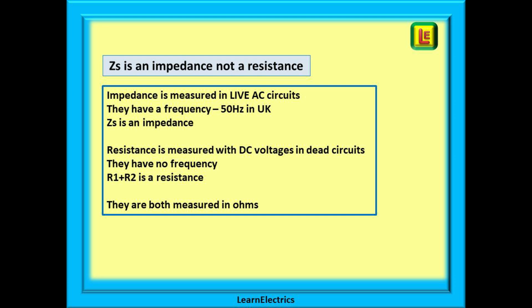First let's clear up a little thing. ZS is an impedance because it is measured on a live circuit alternating current. It has frequency. But resistance in our trade is measured on dead circuits or DC circuits with no frequency. R1 plus R2, for example, is a resistance, a DC measurement on a dead circuit. But they are both measured in ohms and at 50 cycles per second or 50 hertz the difference between impedance and resistance is so small that it is not worth worrying about. So, for me, if you call ZS a resistance or an impedance I would still know what you were talking about.